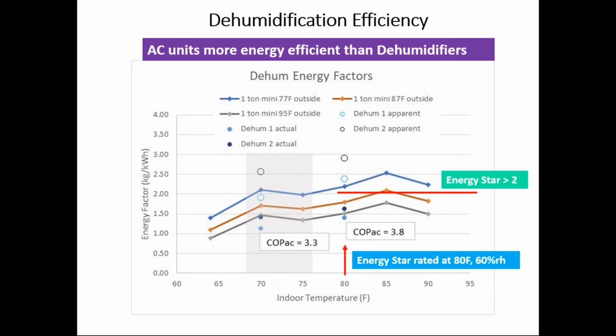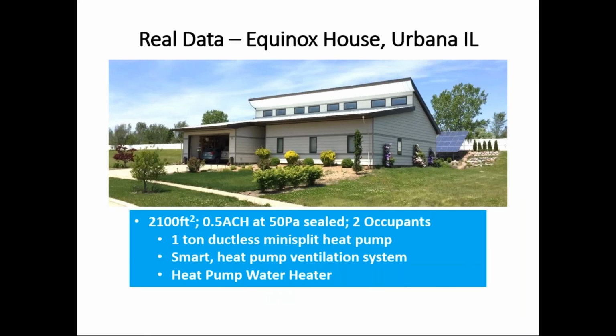And so I show the energy factor drop in those open circles for the dehumidifier as is. But since that heat has to go through an air conditioner, and again I'm using this high performance mini split air conditioner to take the dehumidifier heat out, the solid dots below are the energy factor that accounts for the air conditioning needed to remove the dehumidifier heat out of the house. And you can see that's a pretty significant drop in its actual energy factor. The other result is that you more efficiently remove water with a typical air conditioner than you do through a dehumidifier. So the conclusion is: get as much water out of the air in a home with the air conditioner first, and then a dehumidifier if you can't avoid it.